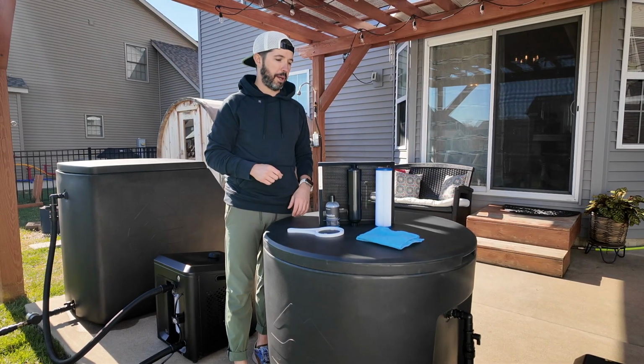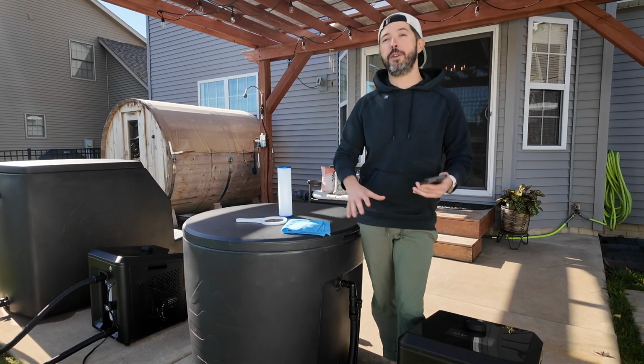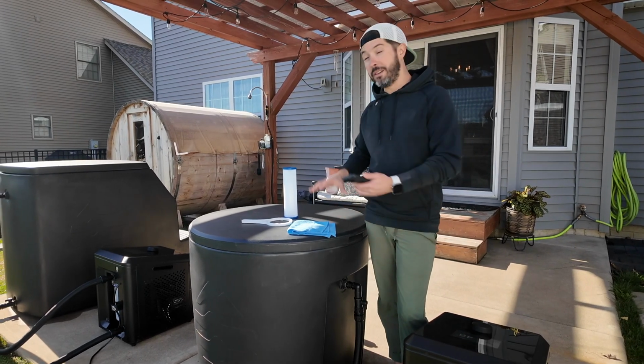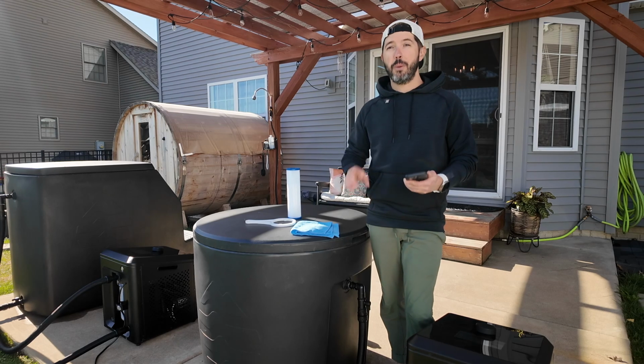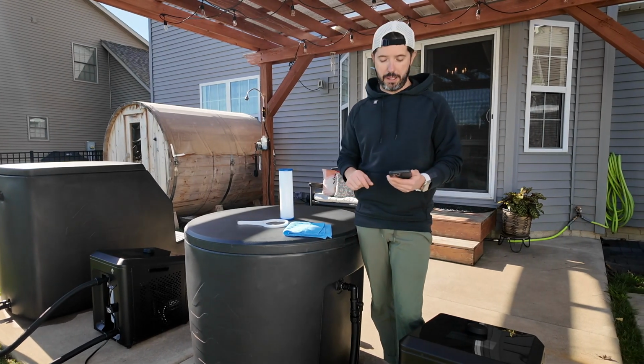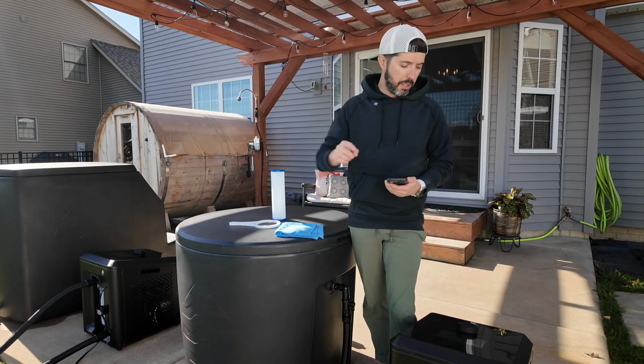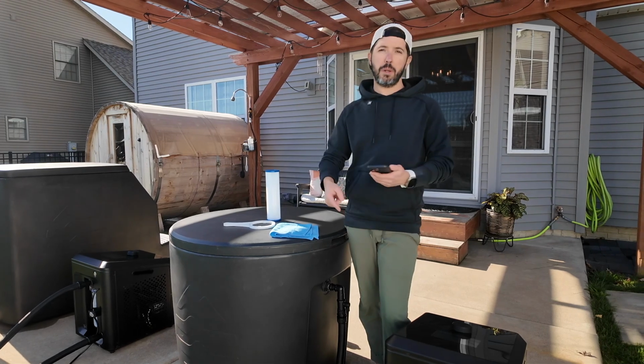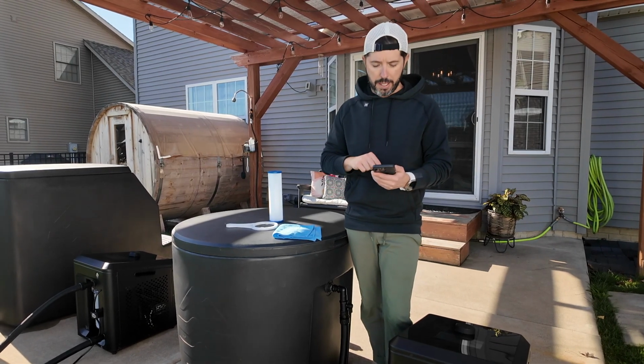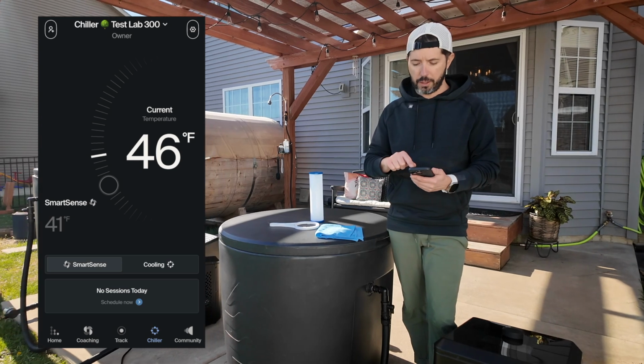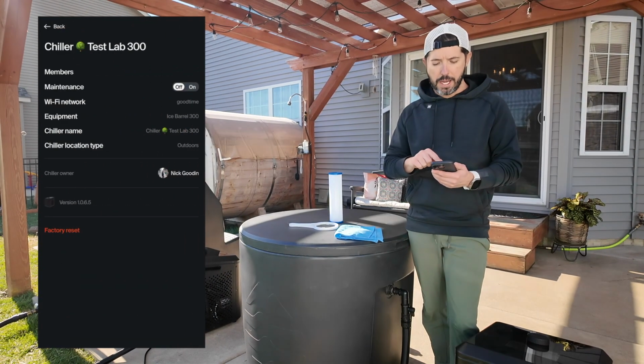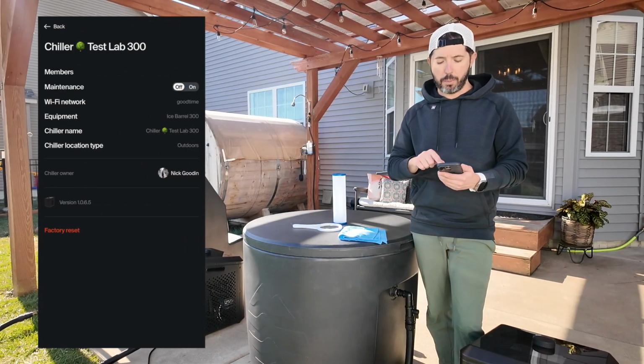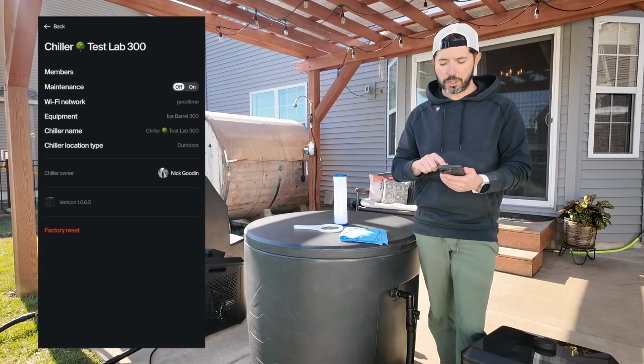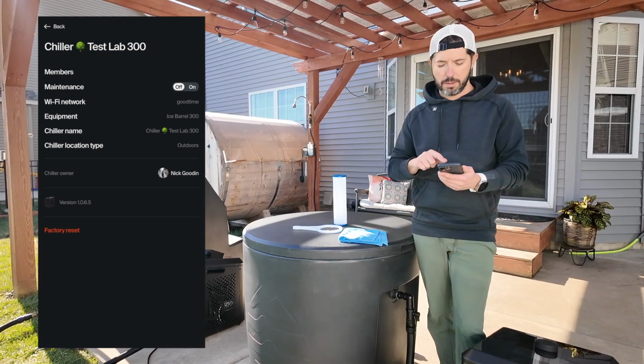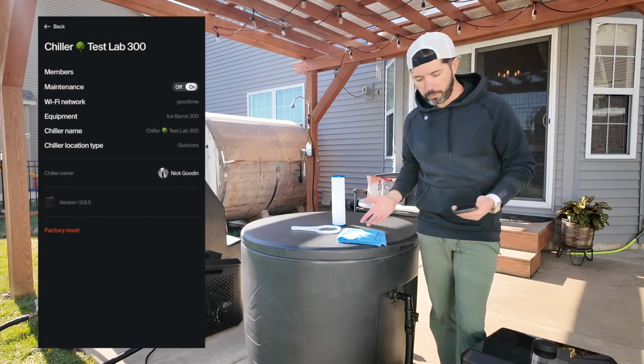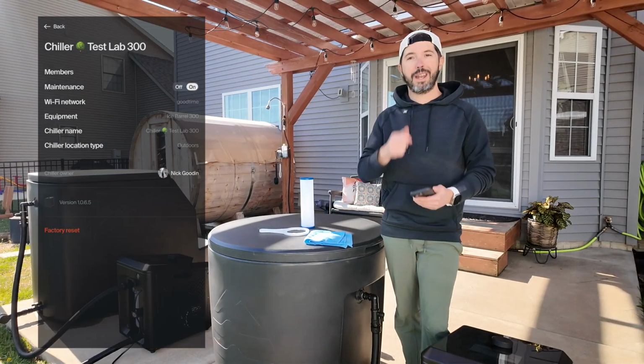Before I show you how to clean the water filter, change it, and fully change out the water in your barrel, we have to put our chiller into maintenance mode. You can do that one of two ways: right there in the menu on your chiller, or today I'm going to use the app. I'm in the chiller section of the app, going up to settings in the right hand corner. The second line below members is maintenance, so I'll switch that to maintenance on. Confirm that, and the water just stopped. Perfect, now we can do some work.